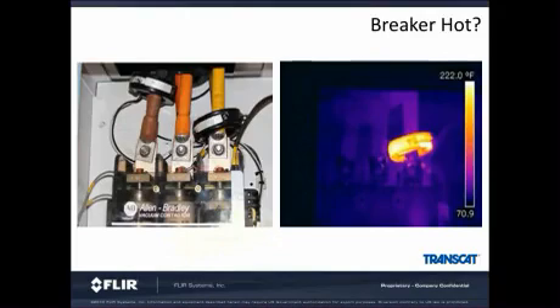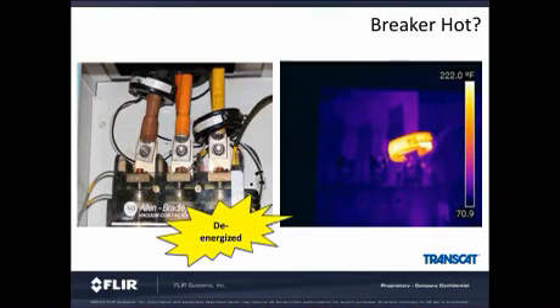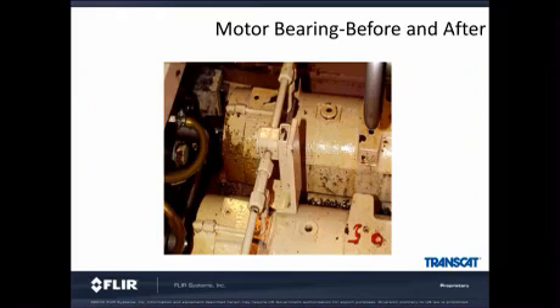Here's an example how a camera can quickly find a dangerous situation. The breaker is de-energized, but the CT is hot. The customer had already repaired this 3 times, but this was an ongoing problem. There was a loose and vibrating connection between the transformer and this connection that made the CT act as if there was current. This would never have been on the list for a normal IR survey because it was de-energized. But the fact that the electrician had a camera at that moment in time, he was able to discover the problem and finally fix it.